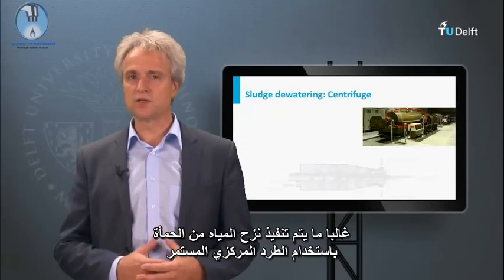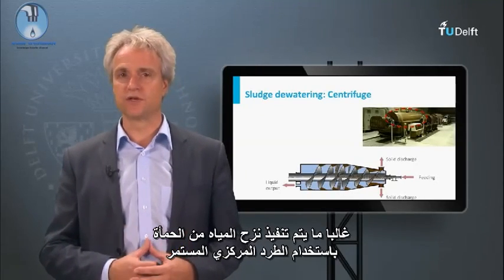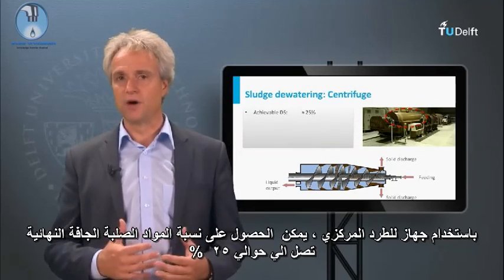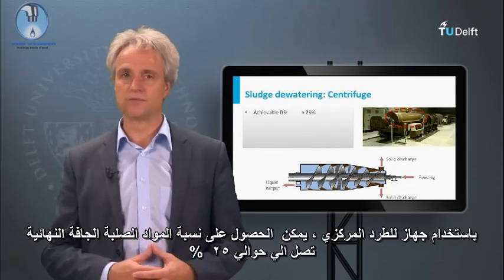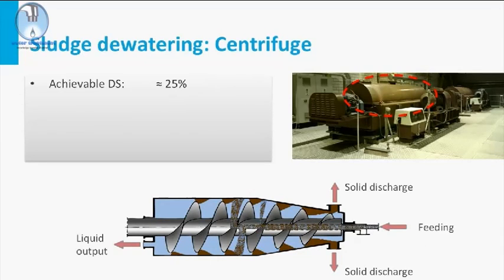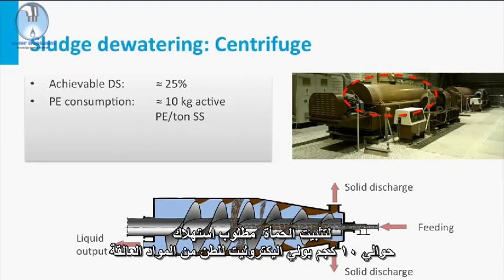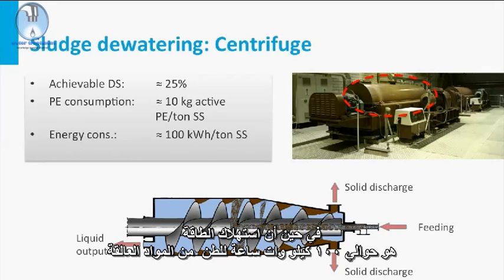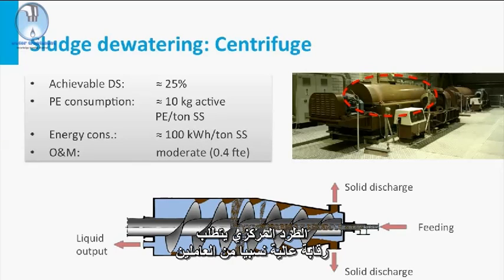Sludge dewatering is often performed applying continuous centrifugation. With a centrifuge, a final dry solids content of about 25% can be achieved. For sludge dewatering, a polyelectrolyte consumption of about 10 kilograms per ton suspended solids is required, whereas the energy consumption is about 100 kilowatt hours per ton SS. Centrifugation requires a relatively high level of personnel attention.